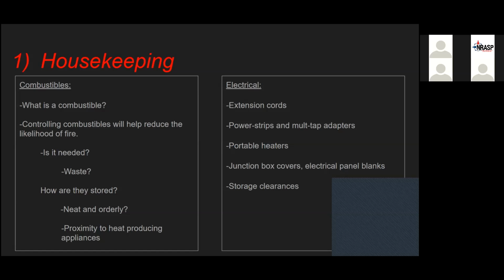Multi-tap adapters, we run into these a lot. Now a multi-tap adapter, according to the International Fire Code, needs to be UL listed and overcurrent protected. Overcurrent protection is different than surge protection. Surge protection actually prevents your appliances from being damaged by surges in power coming through the system. Overcurrent protection is what helps to protect the building wire from overheating by you trying to draw too much power through an outlet. So when you are looking to get a multi-tap adapter, make sure it's overcurrent protected.